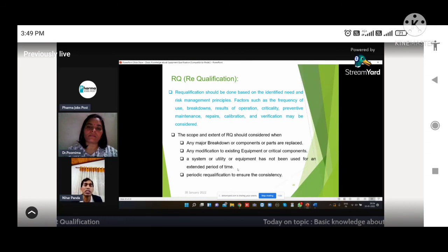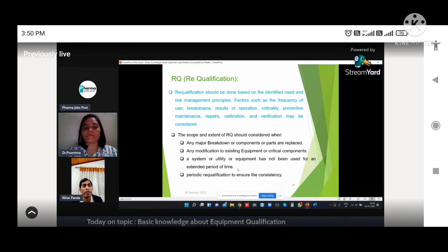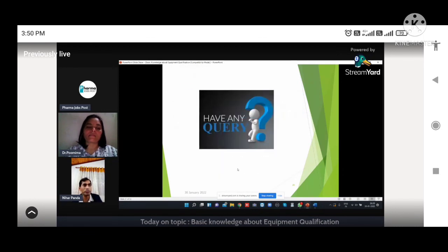All the requalification is based upon your frequency of usage, breakdown maintenance, preventive maintenance, criticality of the equipment, and other parts like repairing, calibration, preventive maintenance, verification of components. All the things need to be checked to decide the RQ. The user has to define the RQ frequency, whether it will be 3 years, 5 years or 10 years, according to user verification or risk assessment. This is all about the equipment qualification. These are the basic things. So many other things are also there, but these are the basic things.